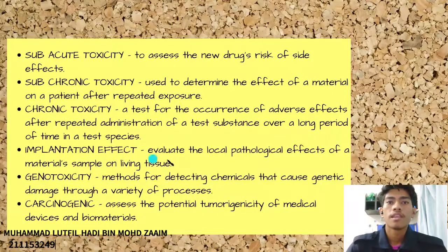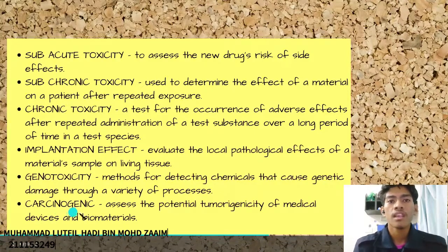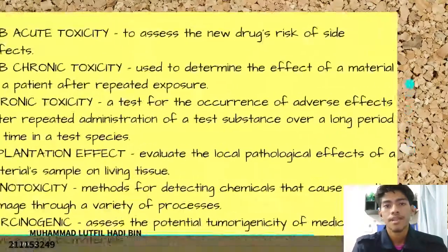Ninth, implantation effect, to evaluate the local pathological effect of a material sample on living tissue. Tenth, genotoxicity, a method for detecting chemicals that cause genetic damage through a variety of processes. And lastly, carcinogenicity, to assess the carcinogenic potential of medical devices and biomaterials. Thank you.